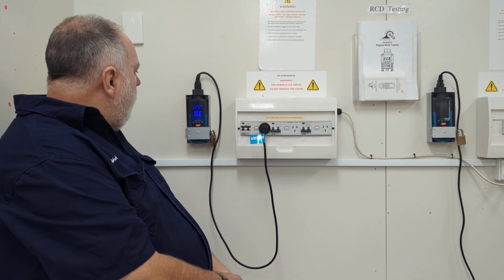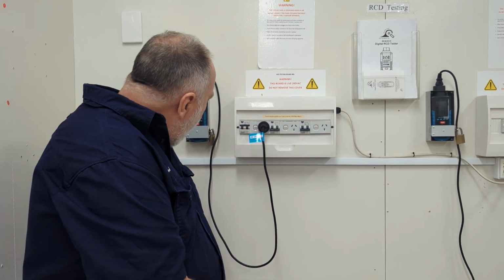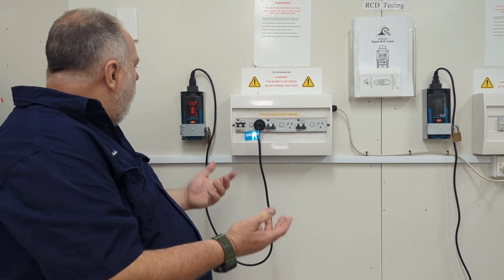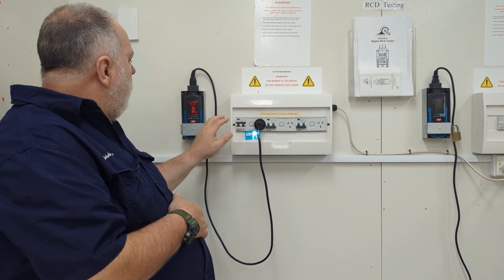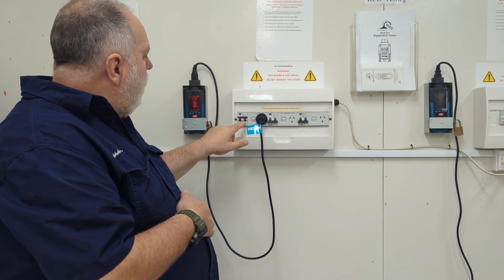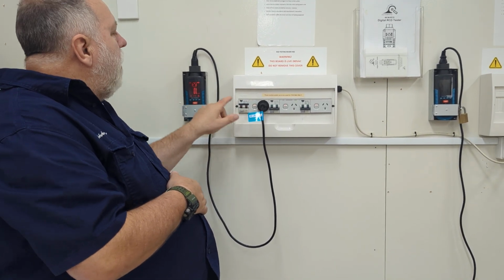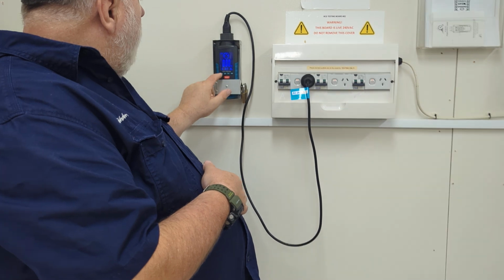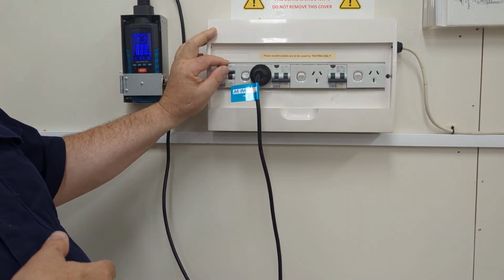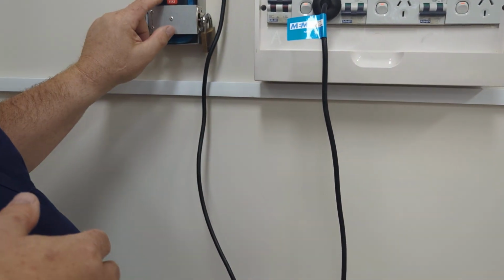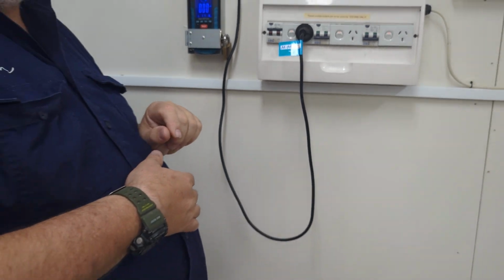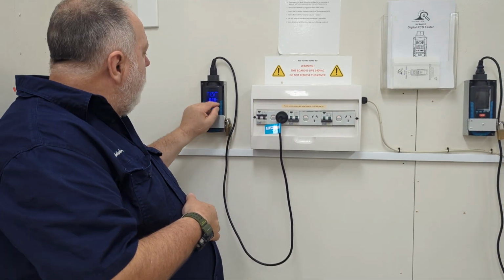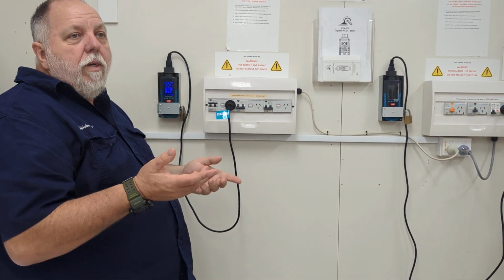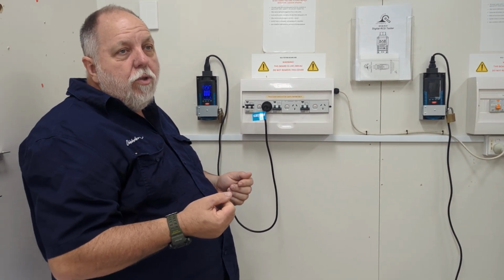So when I push the test button, we go through. It keeps going, might be 20 seconds or not. If I'm right, I might be on the wrong one. But it trips. If it doesn't, it means it's not done. So the other thing is I could have that wrong. I've not got my glasses, but what I'm getting at is that would normally trip. Then you would come back, turn it off, reset it, turn it on, and then set this to your milliamps, all right? So you've got milliseconds, milliamps. The 2 tests required on the paper are defined as the milliseconds and milliamps of what it trips at and what it should be doing.